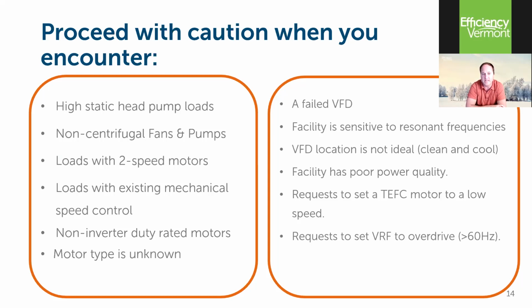VFD locations, not ideal. You need a clean and a cool space for these. They can be put in outdoor enclosures as long as they're properly rated for outdoor conditions. But we don't want them in very hot boiler rooms. And we don't want them in very dusty, dirty environments because they require cooling in the cabinets. There's fans that draw air across the electronics. If that gets plugged up, you have a heat buildup, and the drives don't like that, just like any piece of electronics.